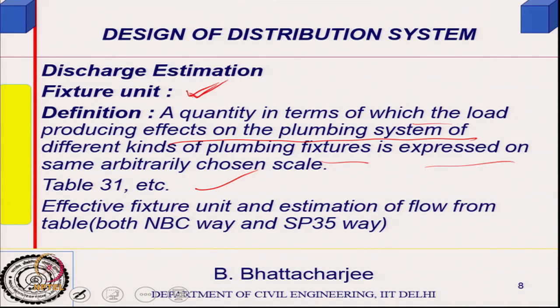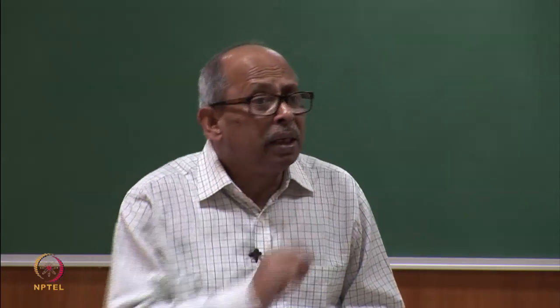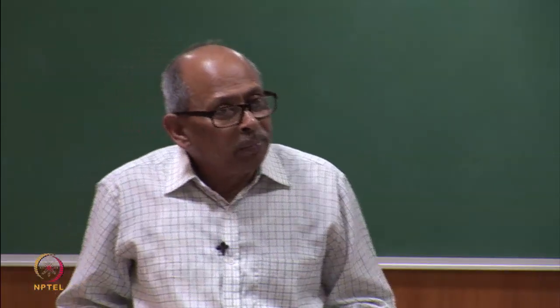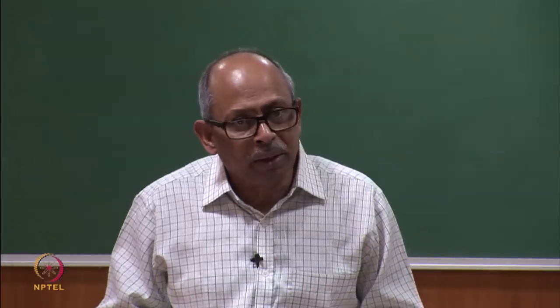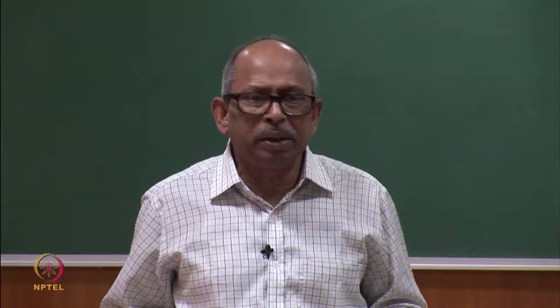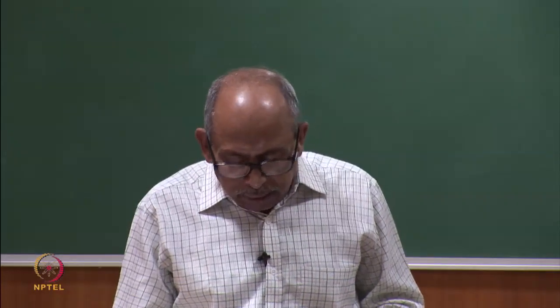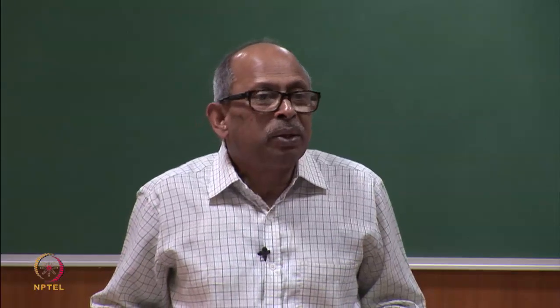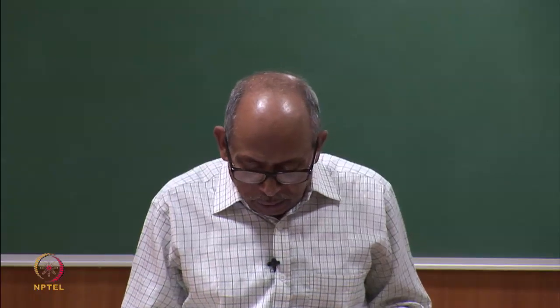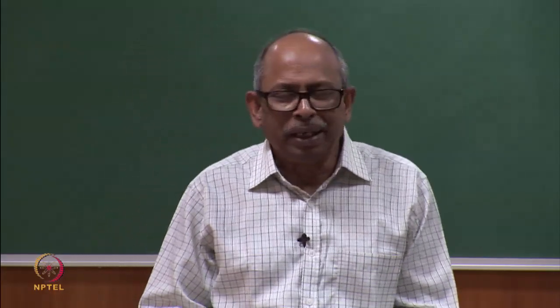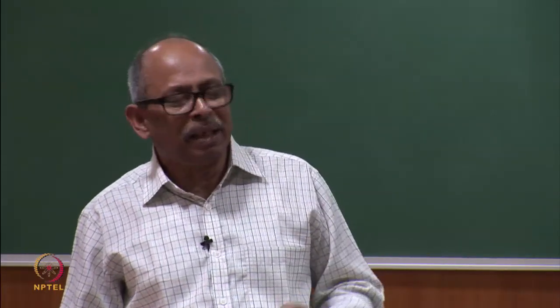For a given floor, knowing how many kitchen taps and bath showers there are, the total number of fixture units can be summed up. Each fixture unit's corresponding flow has been estimated from engineering practice. However, you do not take all the fixture units into your design because of diversity — you take something called effective fixture units, and these values are given in another table in SP 35.